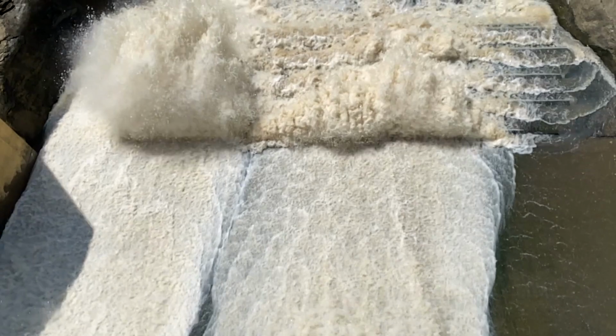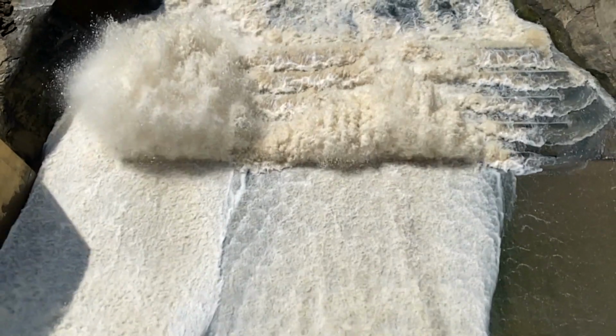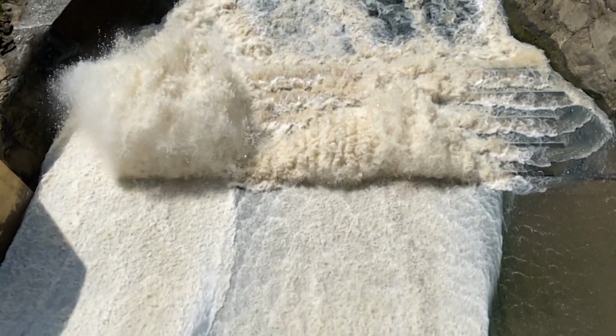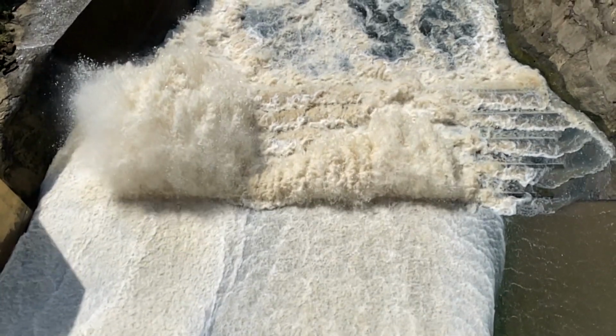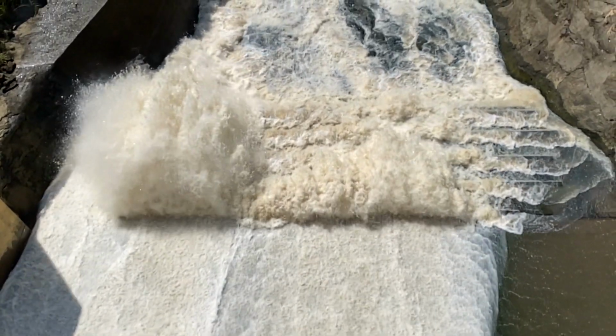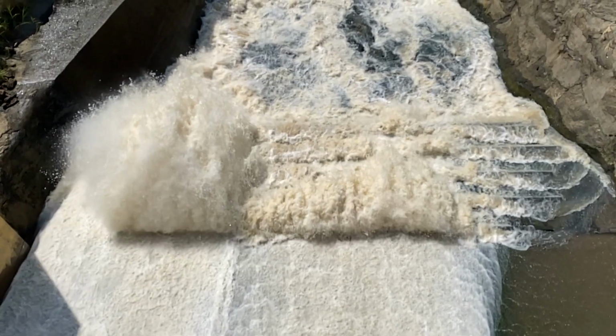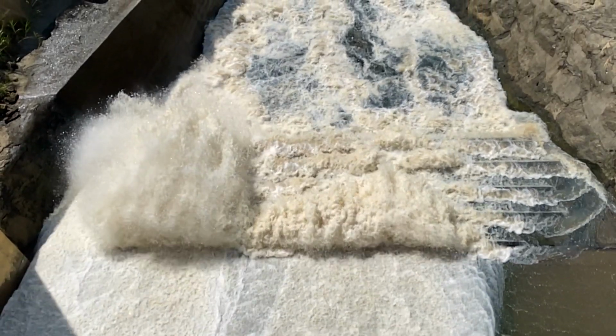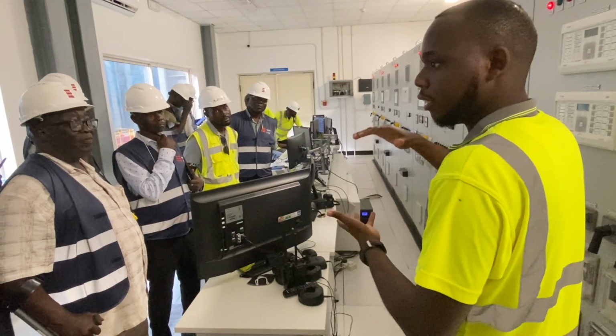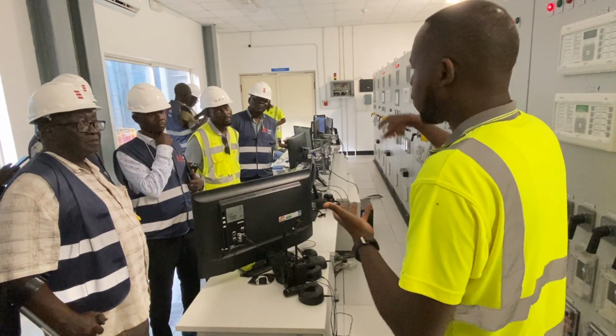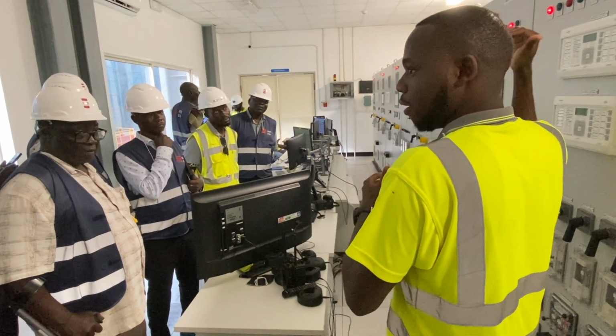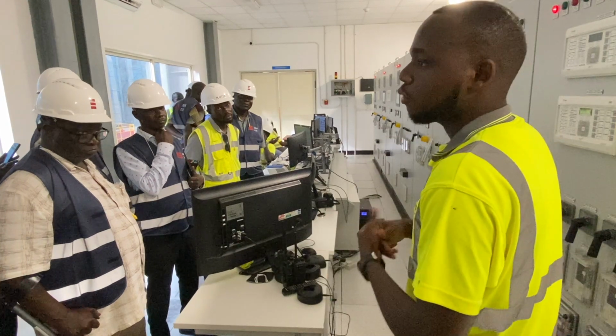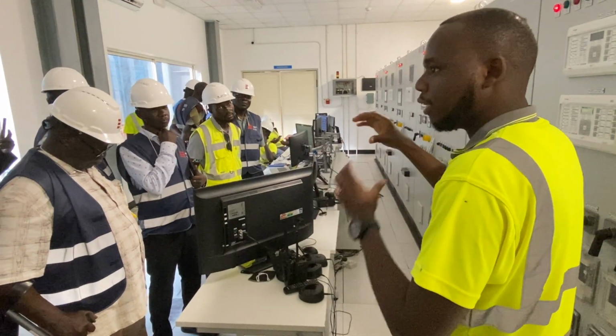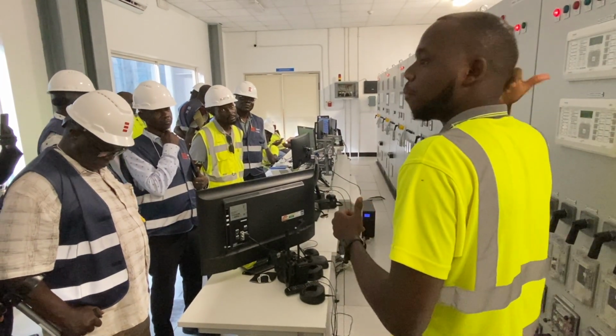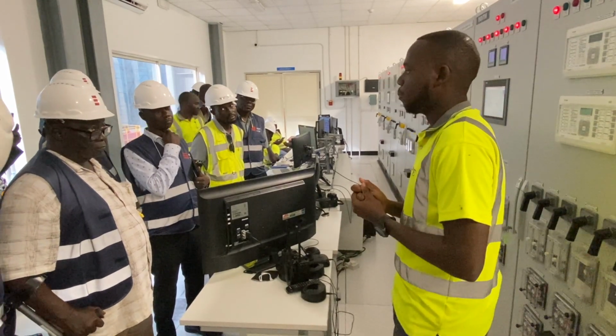The reason we can generate much more there than here is because the net head is higher at HPP1. The difference between the level at the forebay and the turbine at HPP1 is around 53 meters, that's the net head. At HPP2, currently the difference between the forebay level and the tailwater level is 46. Because of that difference, we can generate much more at HPP1 than HPP2.